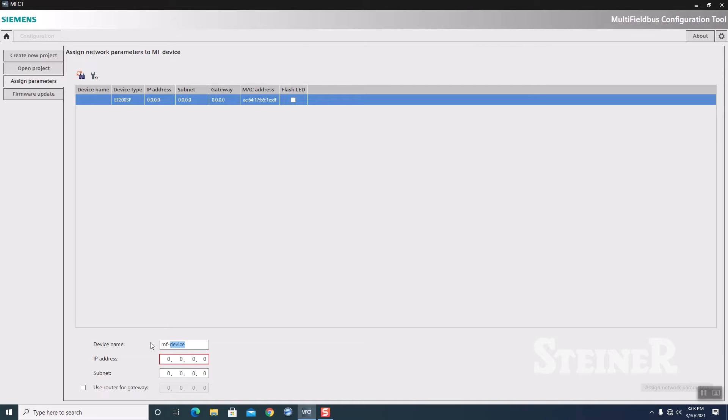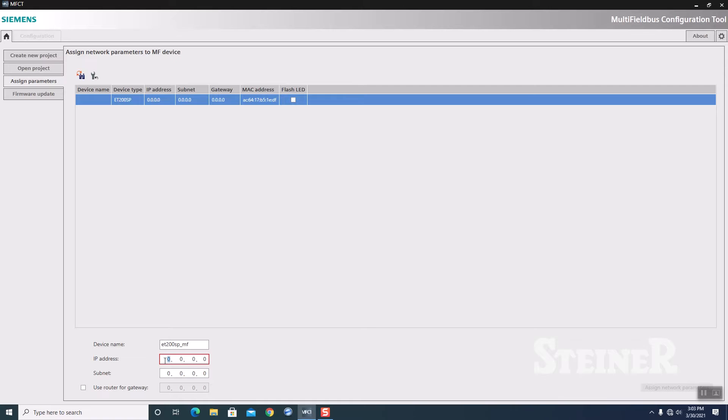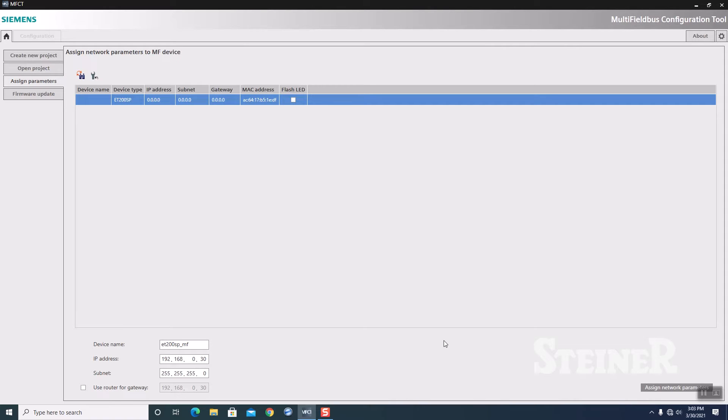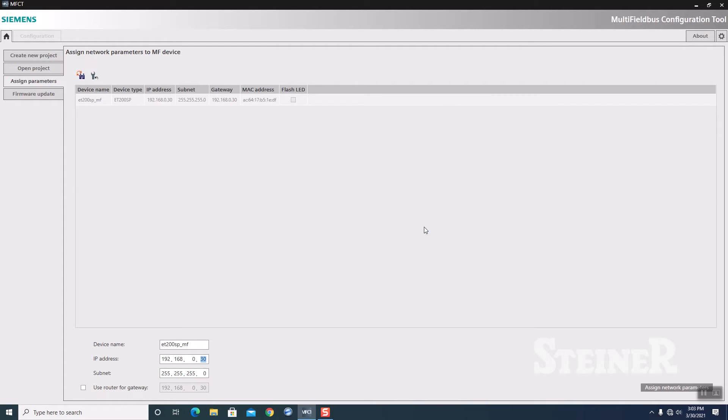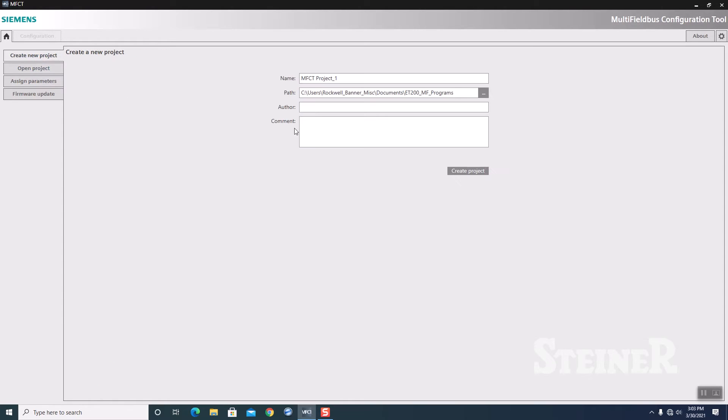It's all at defaults. I'm going to give it a device name, ET200SP underscore multi-field bus. IP of this guy is 192.168.0.30. Once you do that, you hit the Assign Network Parameter button on the right side here. It tells me that my new IP address was set, and I say OK to that.